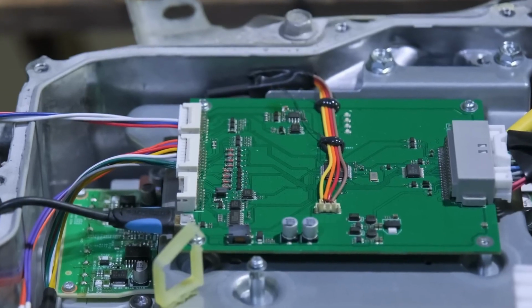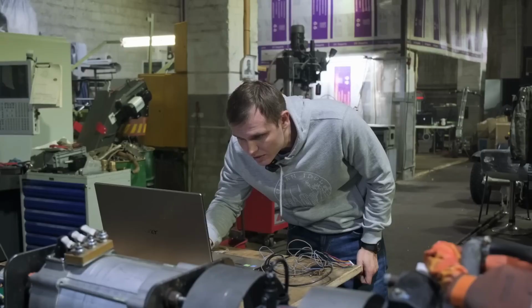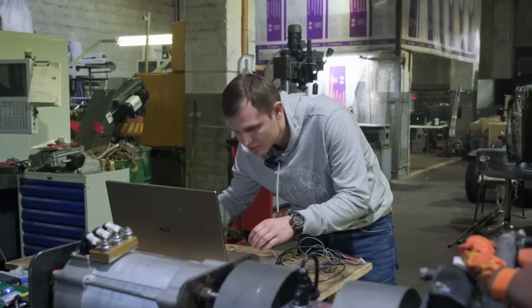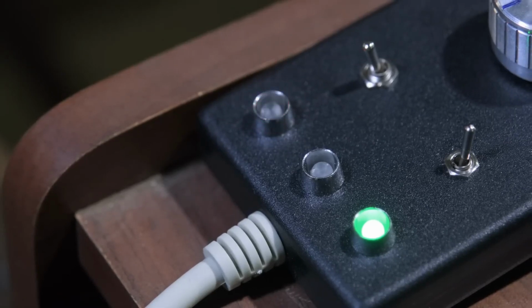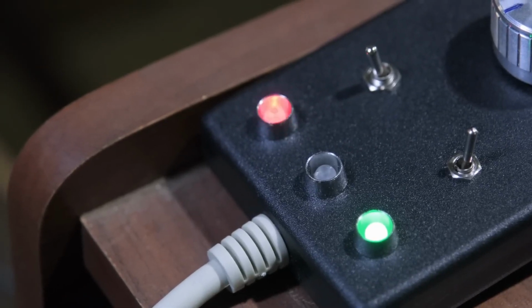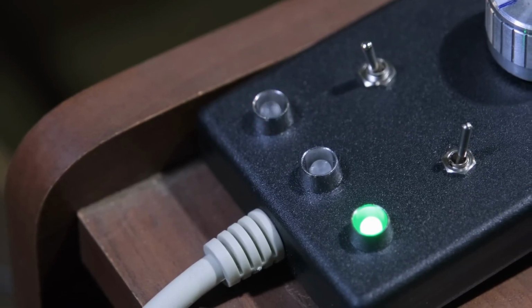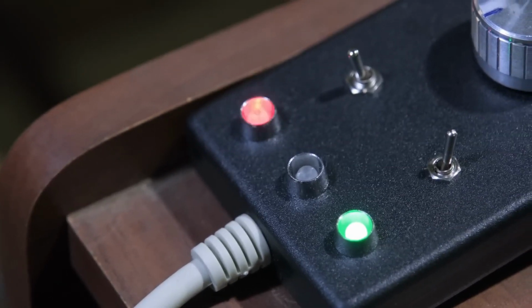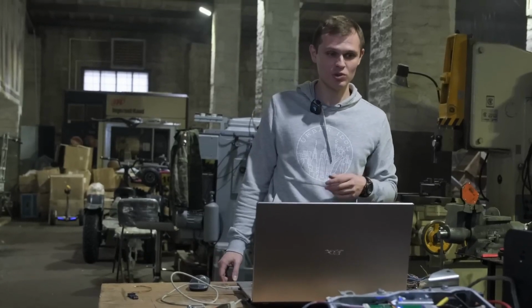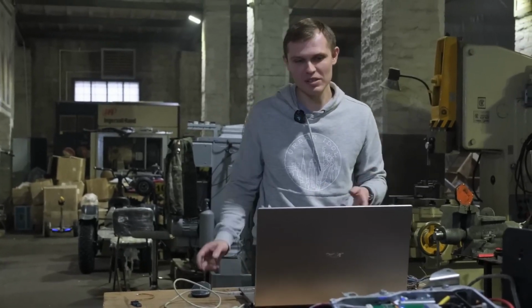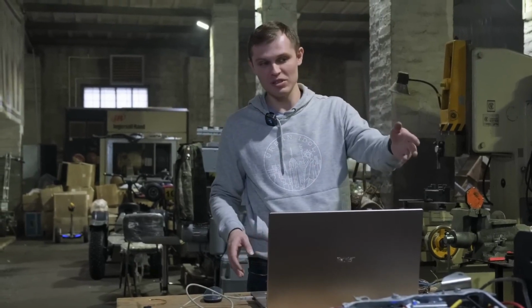We're supplying power. The red light is an error indicator. Right now it shows that there's no high voltage. In other words, no power to the power section. Now I'm trying to start the encoder, or more precisely, to get the system to work with the motor position sensor. Misha, please turn the shaft, try to rotate it a little.